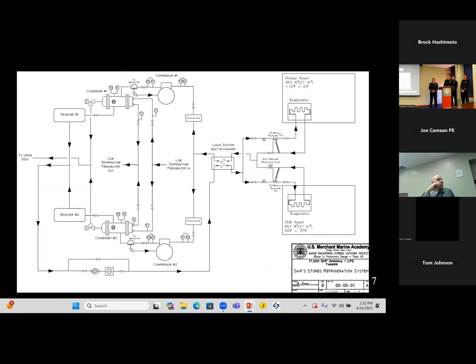The sight glass, you have it shown on the condenser. I think that goes on the receiver. Yes, sir. Okay, now what happens with those is, one of them's going to be in service, the other's probably going to be isolated and secured. Right. Yes, sir. So what happens there is the pressure inside that receiver is dependent on the ambient temperature, which in the case of a fire, could build up an extremely high pressure on that receiver and explode it. So there would be a relief valve fitted on that. And then you don't want any of that stuff leaking out, so there would be a burst disc on the outlet of that. The flow diagram is really awesome. It's just missing some of these details here.